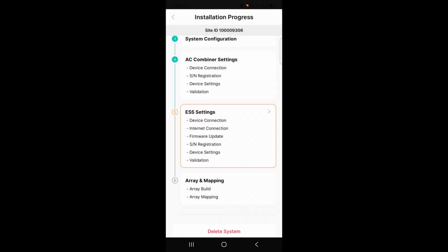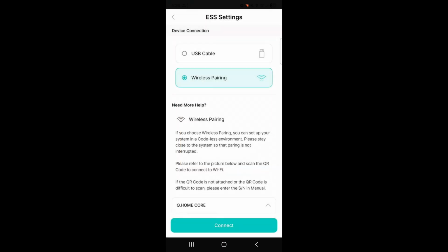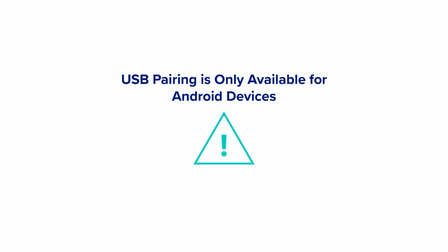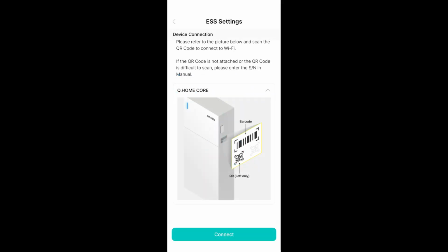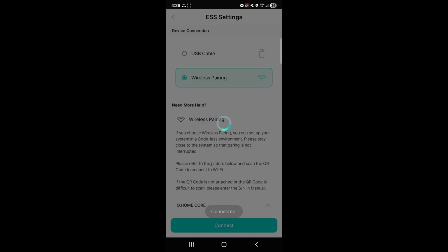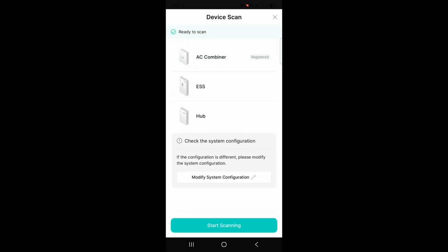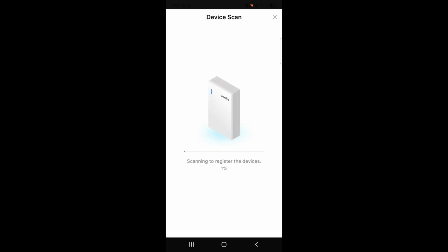Step 5. ESS Commissioning. We will start with the device connection. As before, we have two options: wireless pairing for iOS or Android devices, and USB cable connection for Android devices only. Scan the QR code on the primary ESS enclosure, or enter the serial number manually. Verify that the correct system components are displayed. If there is an incorrect component displayed, select Modify System Configuration to go back and make changes. Select Start Scanning to begin the automatic serial number scan.